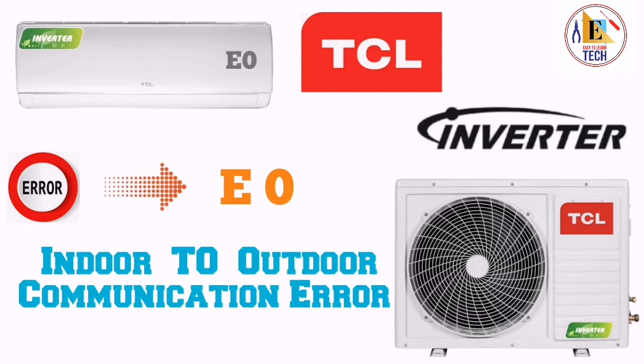Then you have to check the outdoor wire of the communication cable. We have to remove it from the outdoor, then check the DC voltage to see if it is between 13 to 24. If the DC voltage is between 13 to 24 on our outdoor wire, it means our indoor PCB is okay. Then we connect it to the outdoor again.